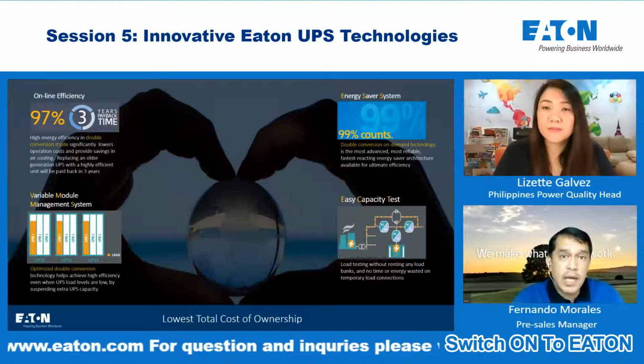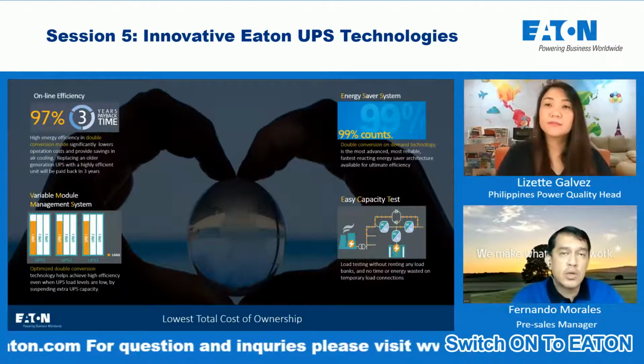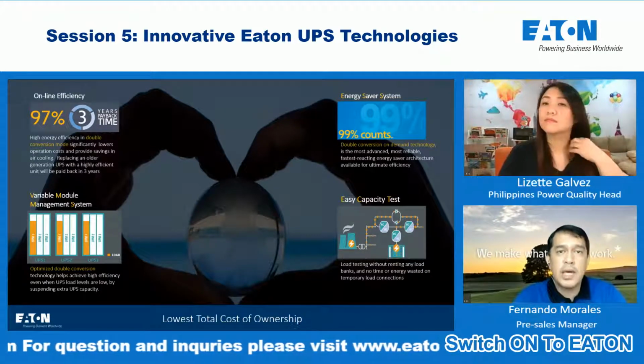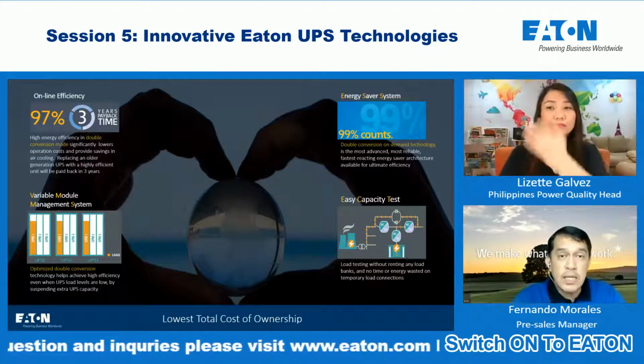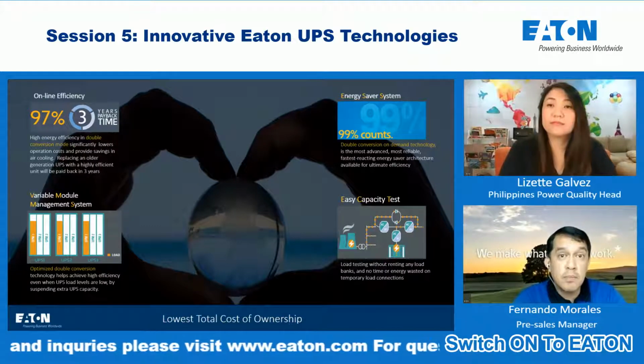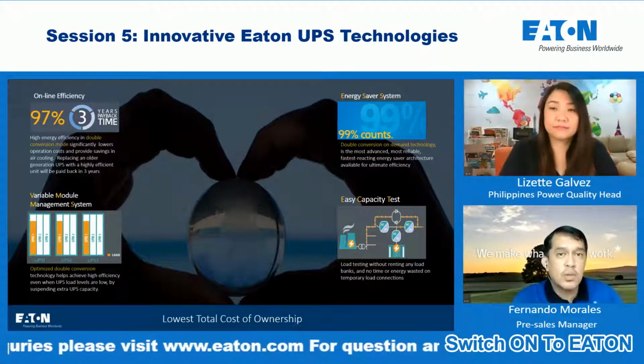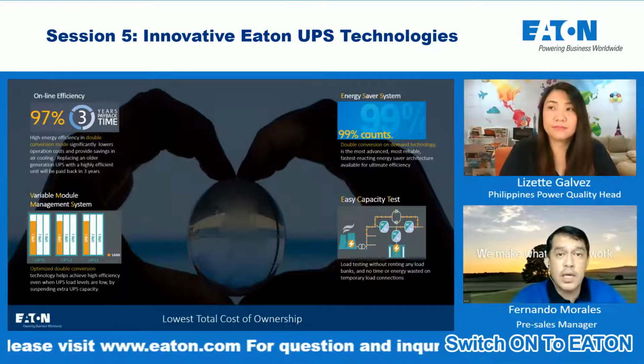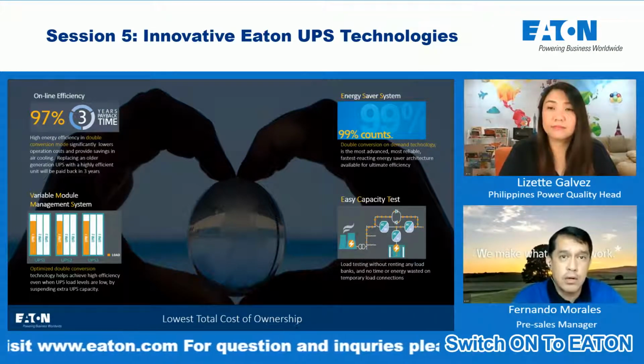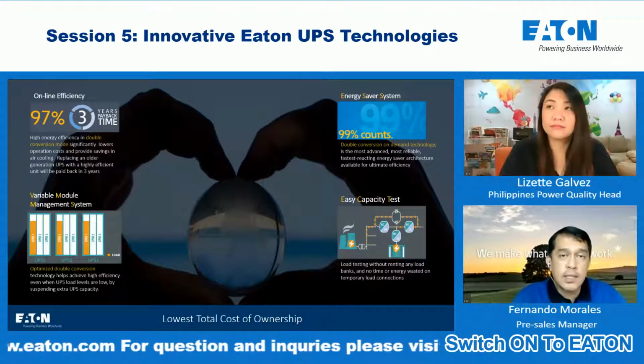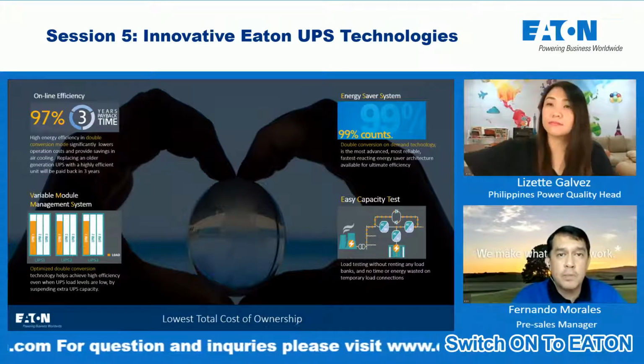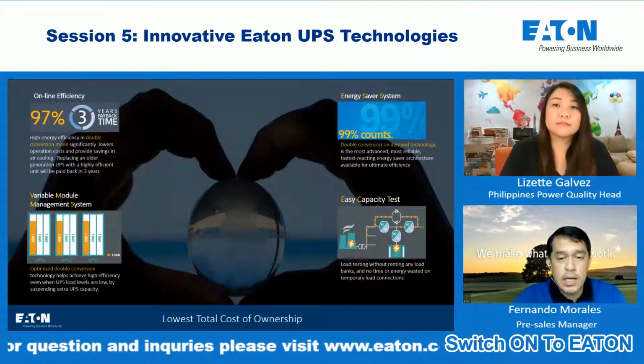Aside from using it during the initial startup of the UPS, we can also use ECT during annual preventive maintenance if the customer can afford a load shutdown, so we can test again the full powertrain of our UPS system using this technology.